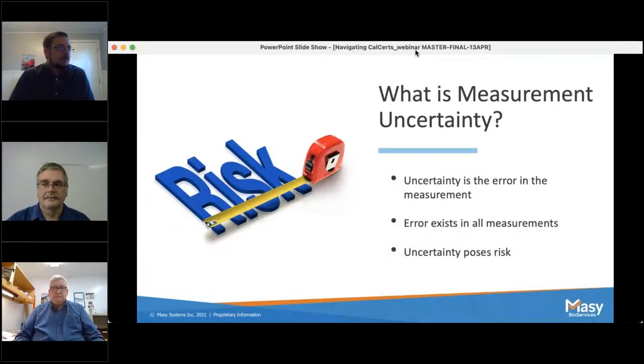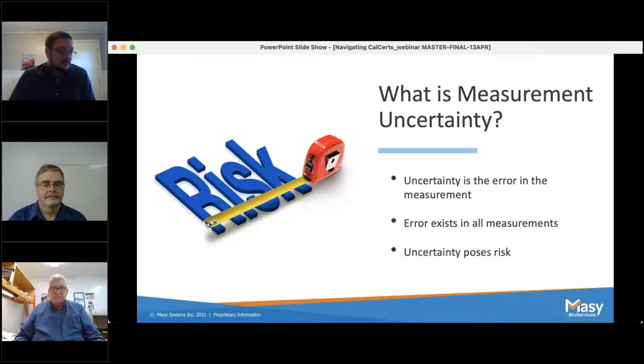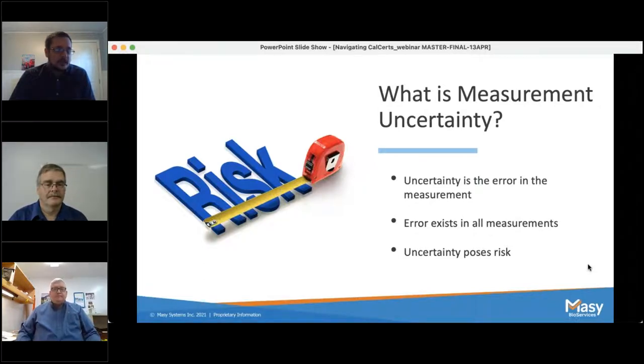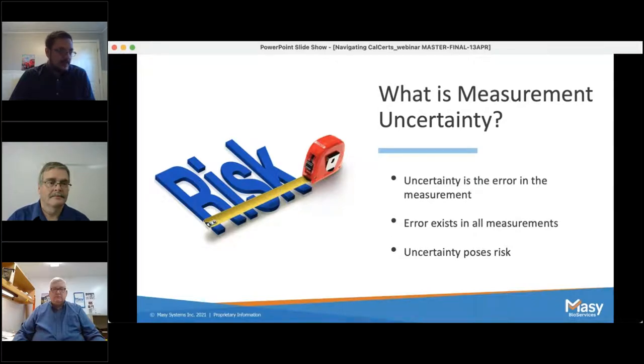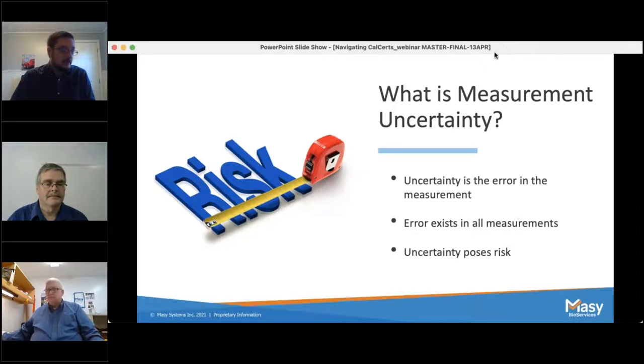Thank you, Keith. So now we're going to delve into measurement uncertainty. In layman's terms, uncertainty is the error in the measurement — that's really all it is. The big thing is: big or small, error exists in all measurements, regardless of the type of calibration or the provider. NIST, for example, which provides the upper echelon of calibrations for the United States, even has some error in their measurements, and when we request a calibration from them, they'll tell us what that is. Uncertainty is error, and therefore poses risk.